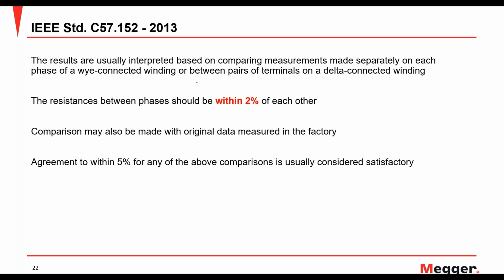And what is the pass or fail criteria for my winding resistance measurements? How do I know what is good and what is bad? The resistance between phases should be within 2% of each other. This is determined by IEEE standard C57.152. This standard says that each of your phases should be within 2% of each other. And a comparison can also be made to the original data measured in the factory.